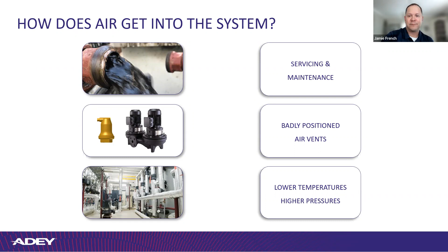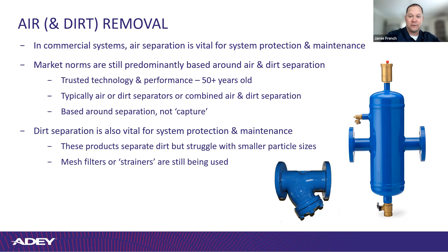So this is the technology that we're used to seeing, right? Air and dirt removal, whether it's individual or combined. 50-year-old technology, been around for decades, but they're based around separation and not necessarily capture, and that's important to note. A lot of these have meshes in them. Some of them have Pall rings where they actually physically knock the debris down into the bottom of it. And how often do these get serviced? I don't know. I don't know many guys that service air and dirt separators. Y strainers, that's the other picture there.